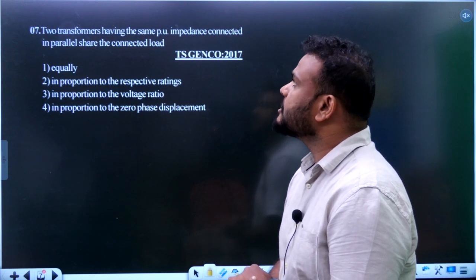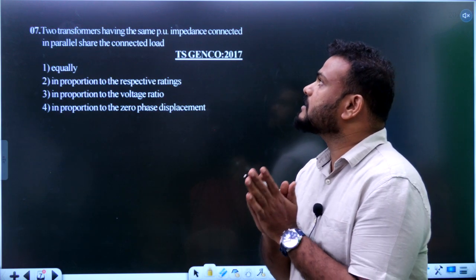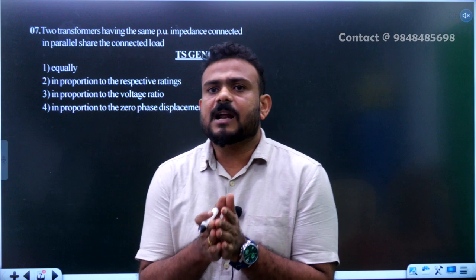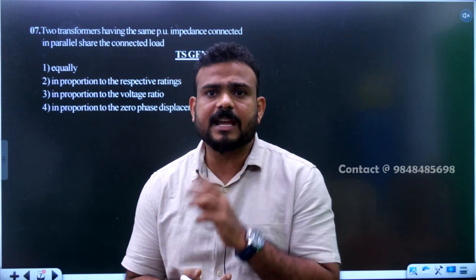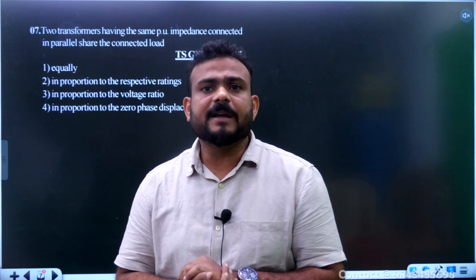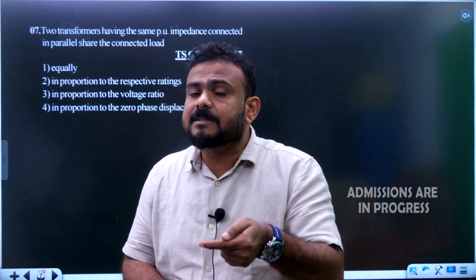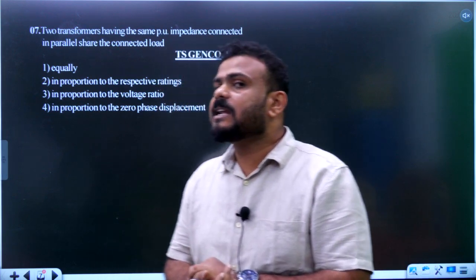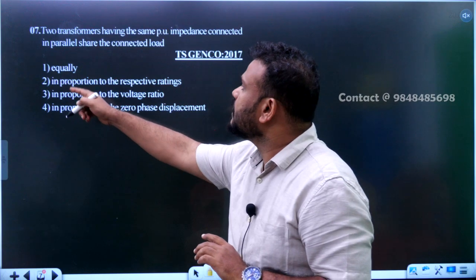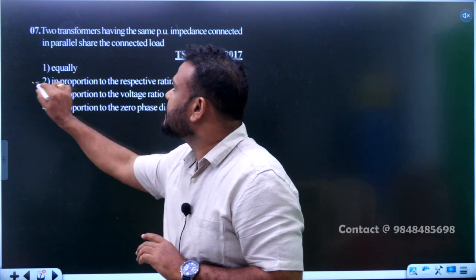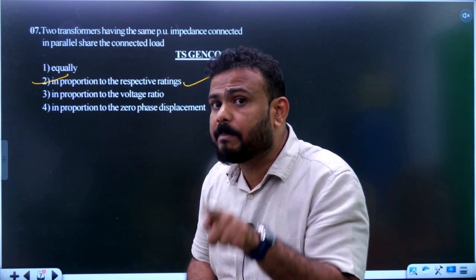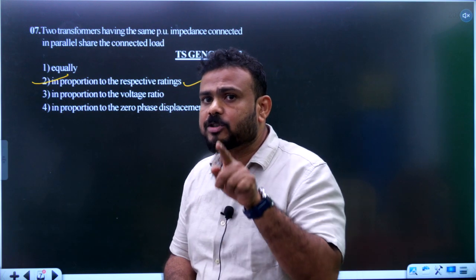Question 7: Two transformers having the same per unit impedance are connected in parallel sharing the connected load. In parallel operation of transformers, the transformer with higher KVA shares more load. The per unit impedance must be calculated with respect to their own base. When per unit impedances are equal on their own base, load sharing is proportional to their KVA ratings — this is the desirable condition.